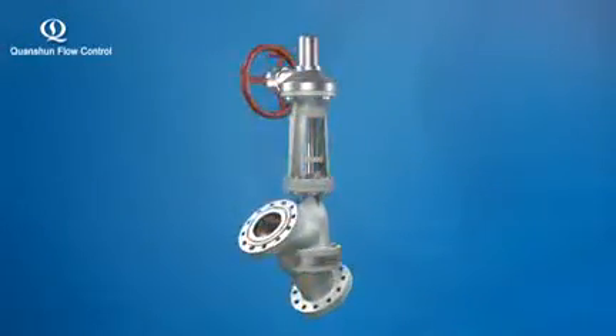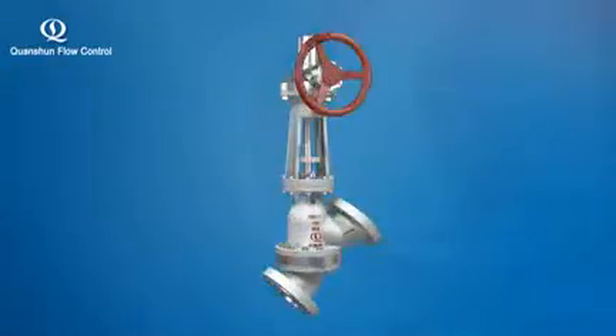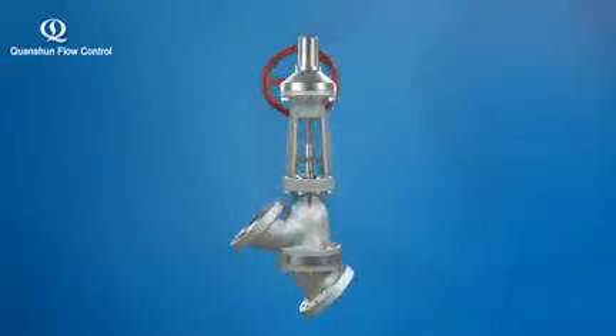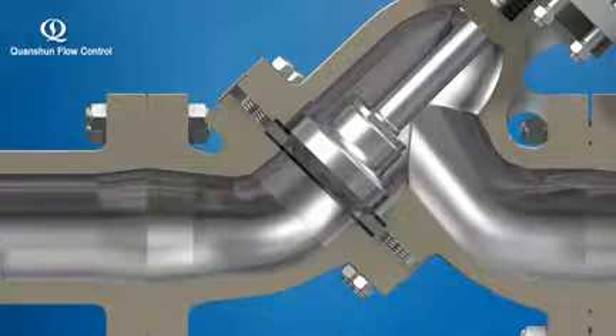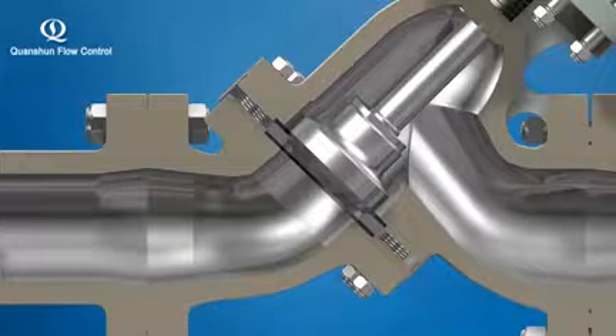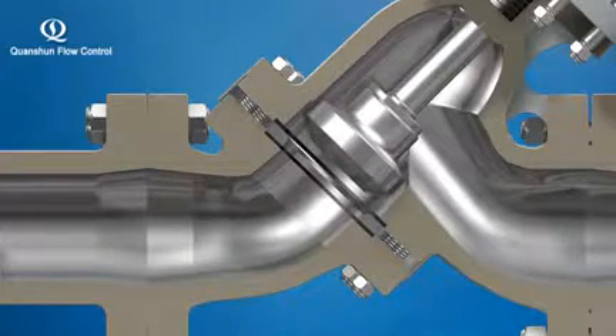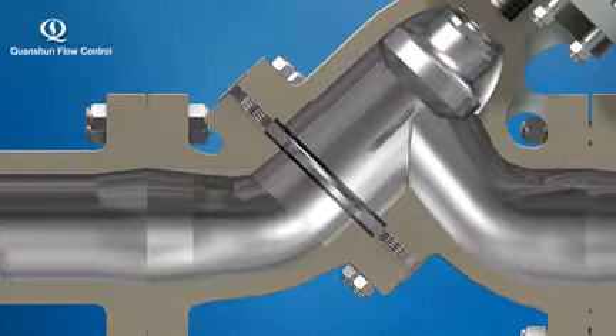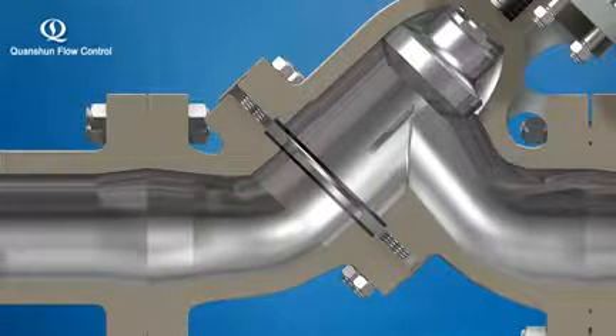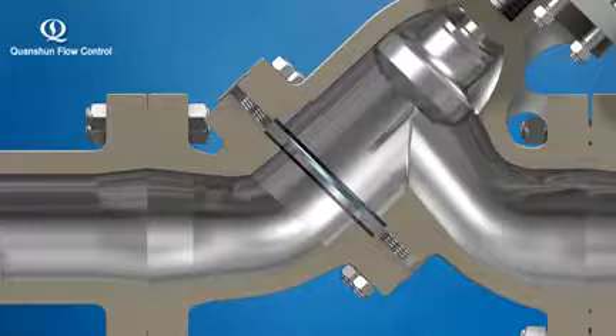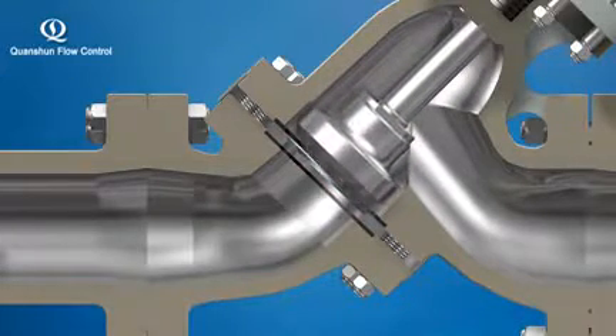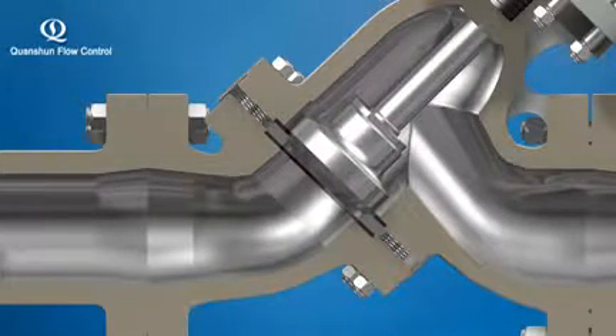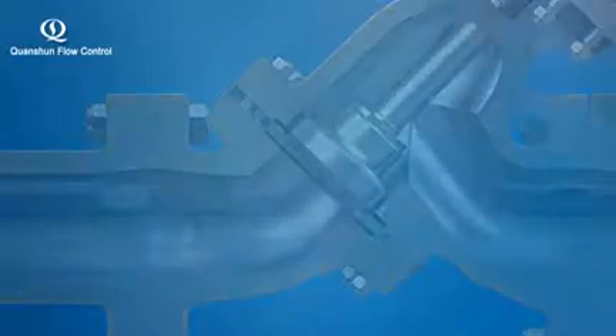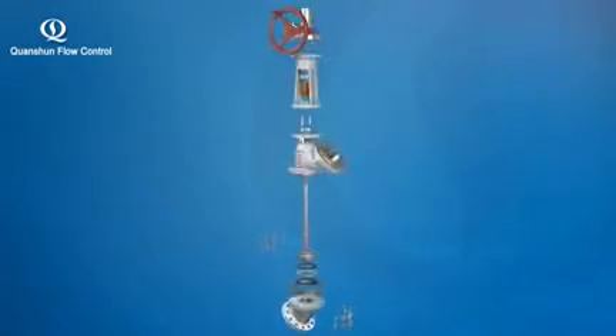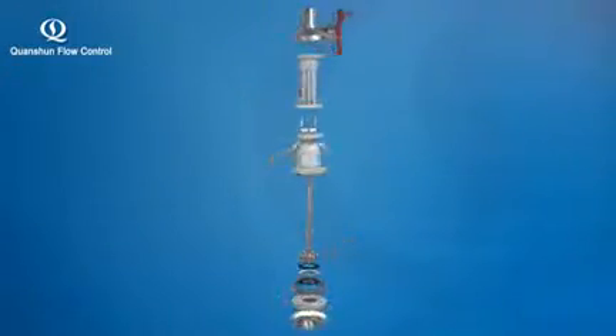9. Airtightness. Based upon the absorption of overseas proprietary technologies, we've made significant improvement with respect to the surfacing materials used on the seal face. The seal face uses cobalt-based high alloy material for plasma arc surfacing, whose hardness, via heat treatment, is adjusted to the optimal state that can best resist the wash, erosion and impact, increasing the seal face strength by at least twice the strength of general valves.